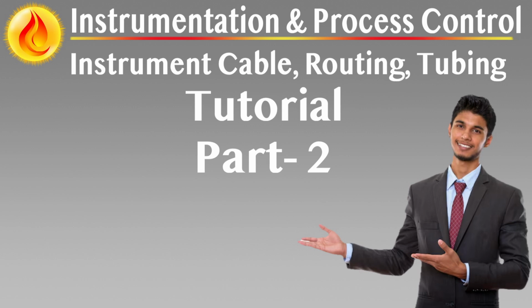Earthing and bonding for personnel safety and signal reliability. Effective earthing and bonding are essential for protecting personnel, ensuring the reliable operation of instrumentation systems, and maintaining immunity from electromagnetic interference. Two distinct earthing systems must be implemented and clearly separated: the safety earth, which protects against electric shock and equipment faults, and the instrument earth, which provides a low noise reference for sensitive signal circuits.